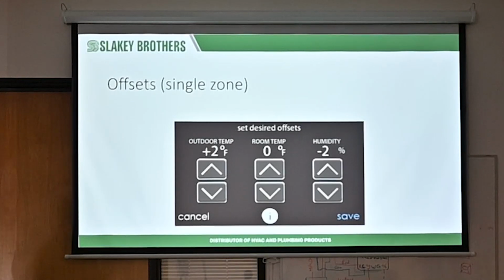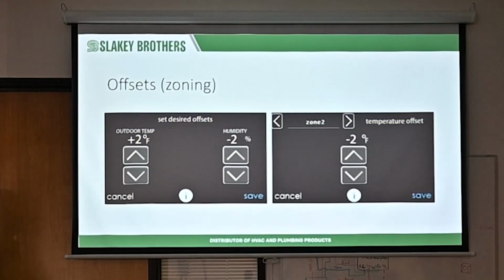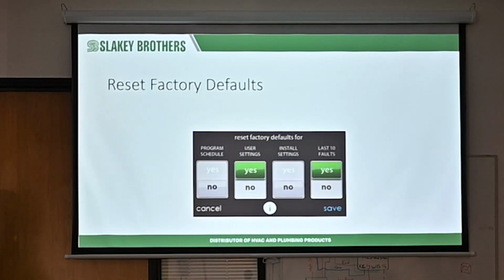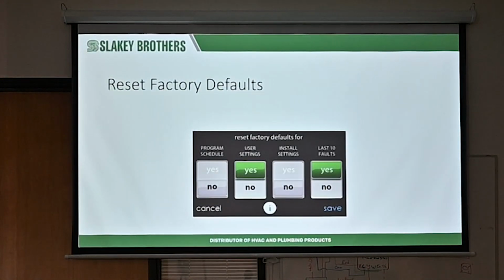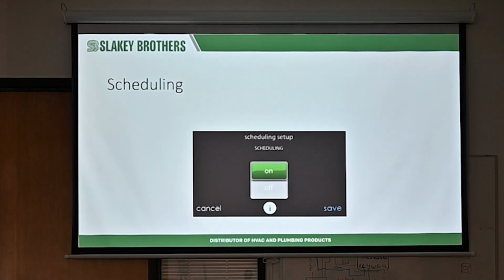But usually in my experience, a thermostat, smart sensor, a remote sensor, whatever it is, once it starts being really crazy, more than a degree or 2 degrees off, there's something wrong with it. It's just the resistance value is starting to get corroded or whatever it may be. You're going to get a new controller, but that's where you can do your offsets for your zoning sensors or your main controller. And if for whatever reason you need to reset factory defaults, you can reset the whole controller through there. Scheduling, again, if you want to have scheduling on or off. Smart recovery, trust me, leave it off.